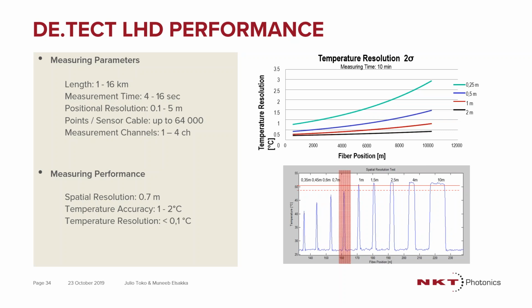Now, what can we reach in terms of performance? As I mentioned, we're doing tunnels, we're doing multiple locations, we're doing linear heat detection applications for tank monitoring, for instance. So it's important to know how far we can use this cable. One advantage is that with the laser light, we can push the distance really, really far. So we can go up to 16 kilometers, and then we can literally put the system in the middle and look at about 32 kilometers both ways.